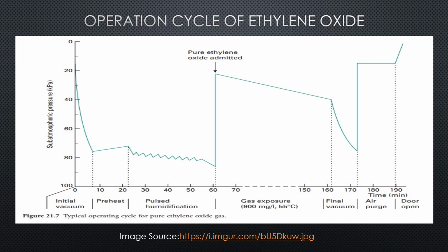Here the forced gas circulation is often employed to minimize the variations in the condition throughout the sterilizer chamber. Packaging materials must be air, steam, gas permeable to permit suitable conditions of sterilization. An individual article in the load must get sterilized. Absorption of ethylene oxide by the load is compensated by introduction of excess of gas at the beginning.